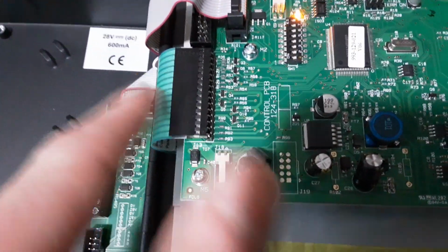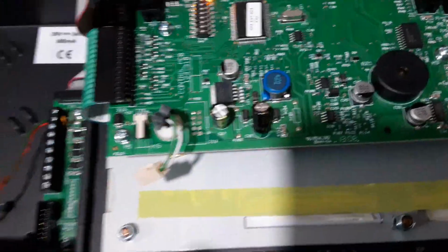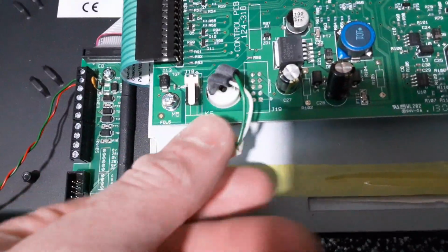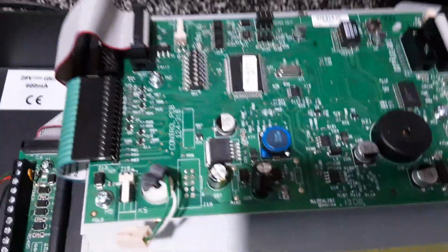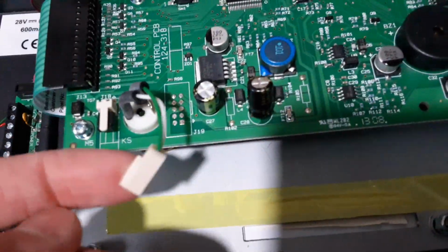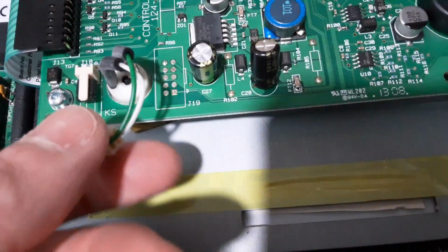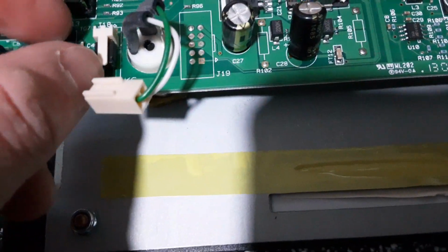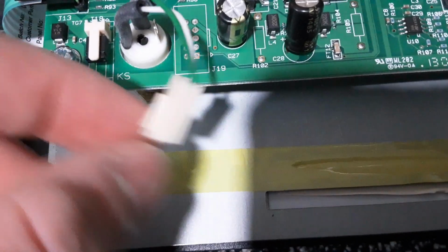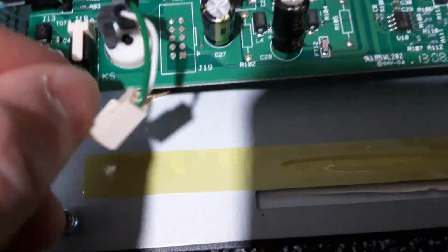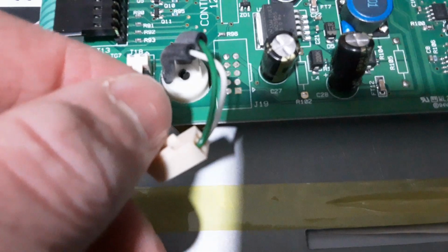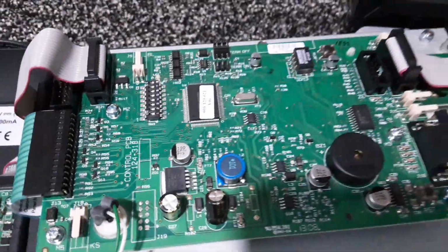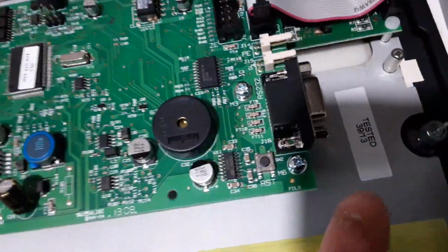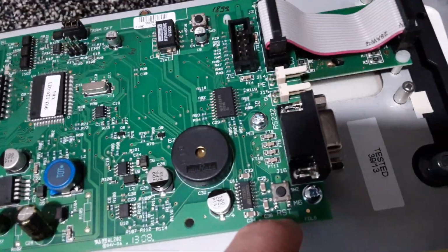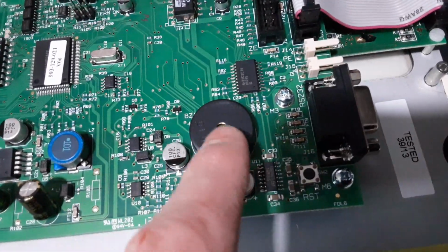That powers the front panel. This is what I was talking about, the key switch. So if you're... Sorry about that. So if your panel has a key switch in it, but you lose the key and it has a connector like this, you can just unplug the key switch and just plug in a jumper block across it. So it then tricks it into thinking it has, what's it, power. That here is a reset button. That's the internal sounder.